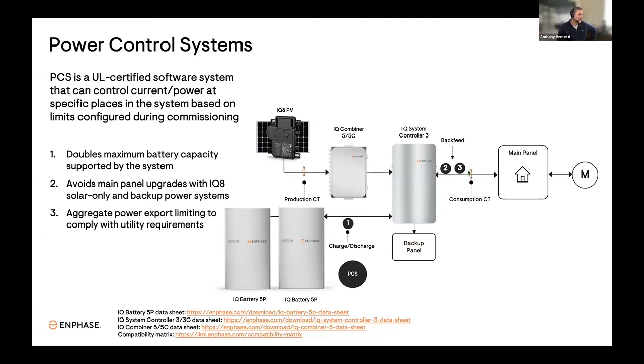So what that means is that the consumption of the backup loads is metered, but the consumption of any loads that remain in the main panel is not metered, because the consumption CTs are over here as opposed to between the main panel and the utility. So for this reason, if a partial home backup system is using PCS and they're in savings mode, the battery is only going to discharge to meet the demand of the backup panel, because it doesn't have visibility over the loads in the main panel.